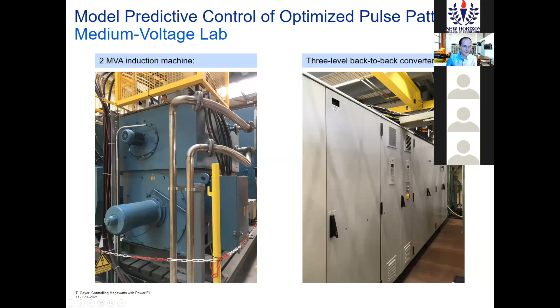Okay, so that's model predictive pulse pattern control. If we use that in the lab, in the medium voltage lab, you have here a 2 megavolt ampere machine with the cooling on top, water cooled. You have the converter.